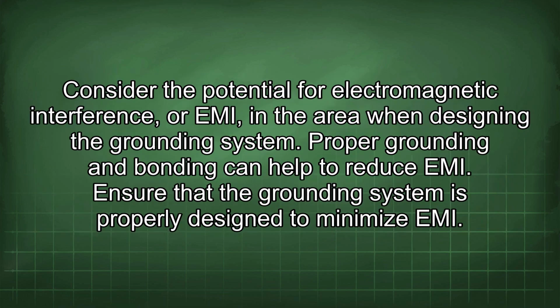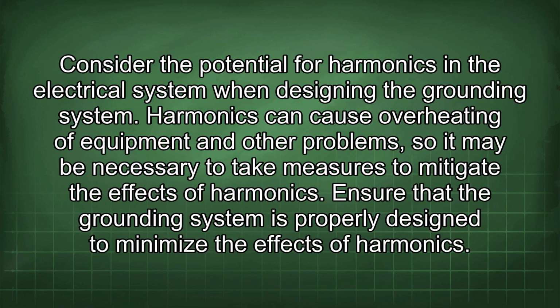Consider the potential for electromagnetic interference, or EMI, in the area when designing the grounding system. Proper grounding and bonding can help to reduce EMI. Ensure that the grounding system is properly designed to minimize EMI. Consider the potential for harmonics in the electrical system when designing the grounding system. Harmonics can cause overheating of equipment and other problems, so it may be necessary to take measures to mitigate the effects of harmonics. Ensure that the grounding system is properly designed to minimize the effects of harmonics.